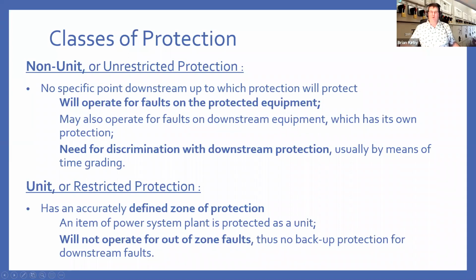Okay, so those are faults we're likely to see. So what type of protection will we be looking at? We have two main classifications, non-unit or unrestricted, and that will operate for a fault regardless of where the fault on the network is. As long as it can detect it, it will operate. So that means if you have a multi-stage protection scheme and your end stage has a fault, the protection on the first stage, if it detects that fault, may operate and isolate more of the network than is necessary. So we need to do some discrimination. And typically that's done by what's called time grading. So you make the protection progressively slower as it gets nearer to the source.